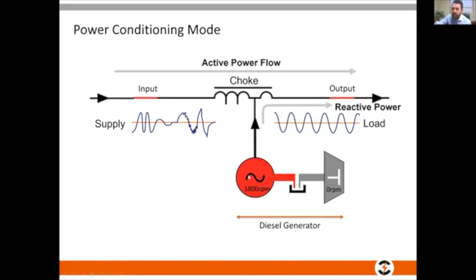That's why we had our flywheel. And you'll see back in the photos that we gave you, we mechanically couple a flywheel to the end of the diesel generator. Why do we do it? Well, in this instance, as I said, I've got a problem. My 5 seconds is the problem. Well, I'm storing so much energy in my flywheel that when the mains fails, when that input breaker opens, and I send a signal to the engine, I also start to release the energy that I've stored. And by releasing the energy, I'm transferring it from this flywheel over to my alternator to make sure that this never slows down. So after 5 seconds, the yellow item will gradually start to drop, again, because it's transferring its energy. But guess what? My alternator, my 1800 RPM never slows down.